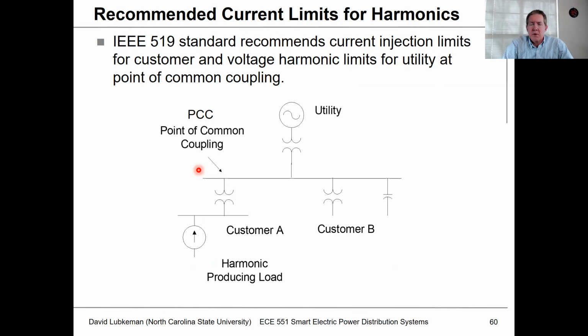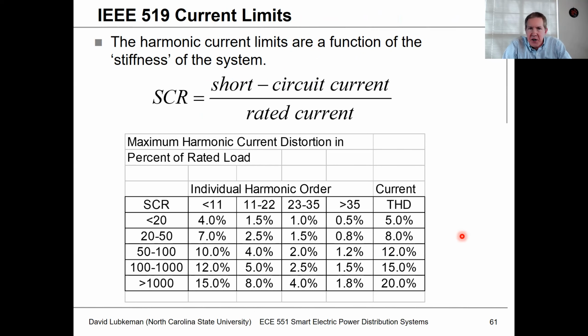Now, there are standards on how many harmonics we can have in a circuit. And this is actually done through this standard called IEEE 519. 519 is incorporated into the DER standard 1547. So they just basically took the whole 519, rolled it into 1547. This standard's been out for a while, but basically what they talk about in the standard is if you have a harmonic producing load, say at customer side A, you're looking at the impact on customer B. And so this interaction point would be at the point of common coupling. This is a common bus between the two nodes. And so we're looking for how customer A would maybe impact this voltage and cause something bad happening at their neighbors. You've got limits on currents that can be injected at the harmonic levels.